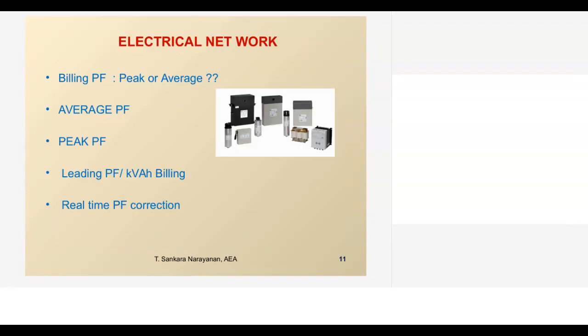Second thing, we have to look at the power factor. Mostly the billing we get once a month is taken for a 30-day or 28-day interval. So billing power factor is basically total kWh divided by kVAh. So they take the monthly average. Why do we take the average? Not all industries will have 100% load factor. Some industries have a load factor of 28%, some have 48%.